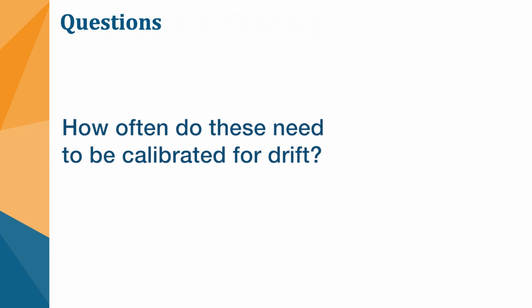How often do these need to be calibrated for drift? Typically, these don't really need to be recalibrated for drift all that often. If you are getting some odd readings or things like that, they can be recalibrated, but typically these don't need a ton of recalibration for a certain amount of time. At least most of these we're outsourcing from other manufacturers. We don't build these in-house, and we don't have any current requirements for, say, recalibrating annually or semi-annually for drift.